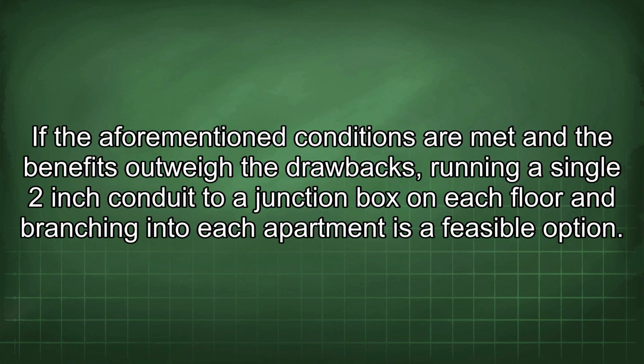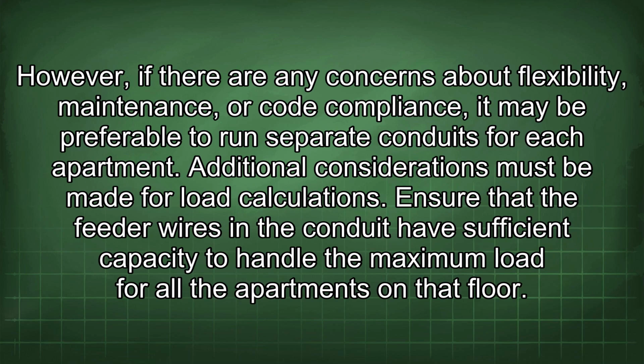If the aforementioned conditions are met and the benefits outweigh the drawbacks, running a single 2-inch conduit to a junction box on each floor and branching into each apartment is a feasible option. However, if there are any concerns about flexibility, maintenance, or code compliance, it may be preferable to run separate conduits for each apartment. Additional considerations must be made for load calculations.